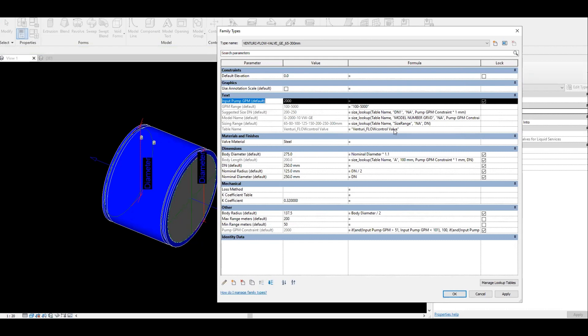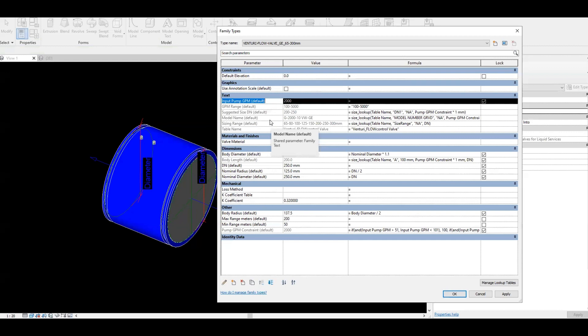When you select this automatically, it will suggest the sizing based on the input pump capacity. We also have the model name here. When you select the correct pump capacity and then select the sizing — say 200 to 250 millimeter — it will suggest the model name for that. Literally, we converted the specs table from the manufacturer into all the Revit parameters, so it's much easier to select here. No need to open the specs table again because we've already translated it from the PDF table to the Revit table with formulas.